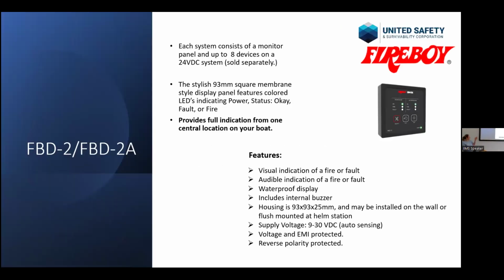This is the simplest version we do, FBD2, small display. It's got audible visual, allows you to monitor 2 zones at the same time. Each zone can have up to 8 detectors, so you can split. You can have detectors for machinery space on one zone and accommodation on a second zone. 24 VDC power, very simple, 2-wire system.